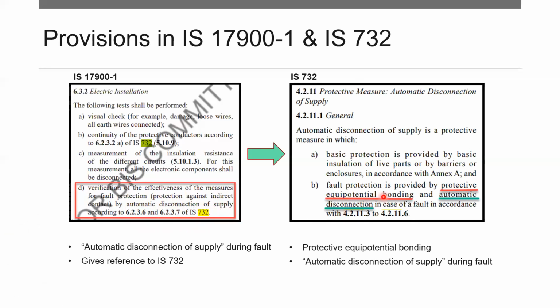And now when you talk about the IS 732 requirements, it is basically talking about the basic protection as Mr. Gopal Kumar was mentioning, and also the fault protection using the protective equipotential bonding and the automatic disconnection in case of fault. So these two have to go in combination. This is very, very important to understand.